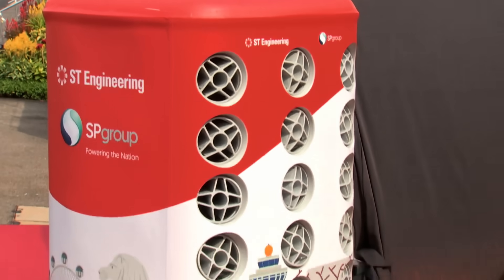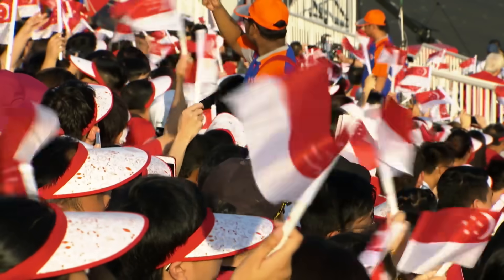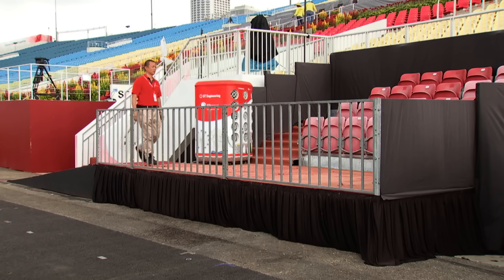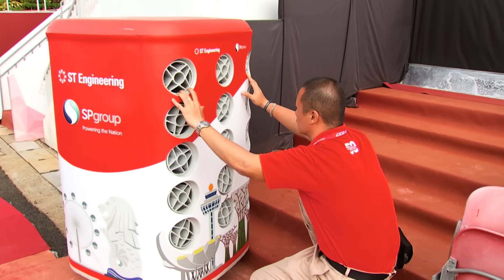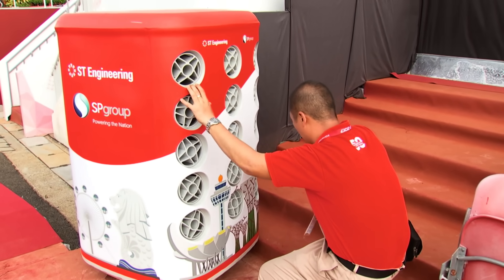The same system can also be adapted for outdoor spaces. We did outdoor cooling at one of the National Day parades in Singapore. Water that comes back from the buildings — what we call chilled water return — we don't want it to come back too cold. So we pipe some of the return water into outdoor cooling hubs that dissipate cooling meaningfully. This improves the temperature of the water going back into the system, making the entire system operate more efficiently.